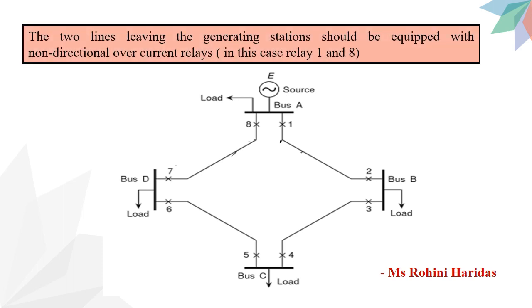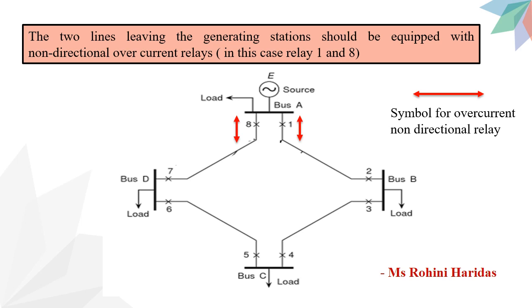The first rule is that the two lines leaving the generating station should be equipped with non-directional overcurrent relays. In this case, those are relay 1 and relay 8. Relay number 1 is equipped with the non-directional overcurrent relay, and similarly relay number 8. This is the symbol for the non-directional overcurrent relay.